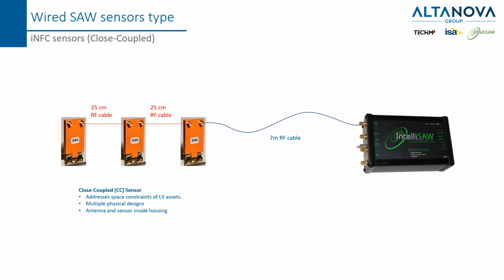For other monitoring applications, IntelliSAW also offers a so-called close coupled sensor, CC sensor. They are addressed to space constraints of low voltage assets. There are multiple physical designs, but they are not wireless. This is the main difference from the standard medium voltage sensor. The maximum distance covered between the reader and this CC sensor is 7 meters, and they are connected through an RF cable.